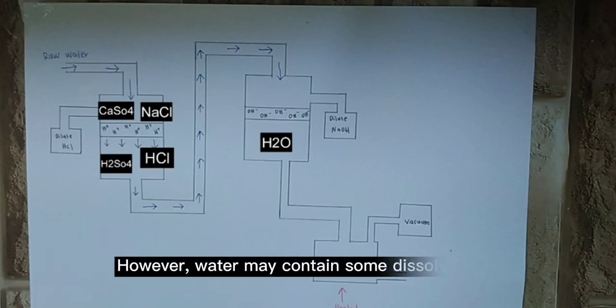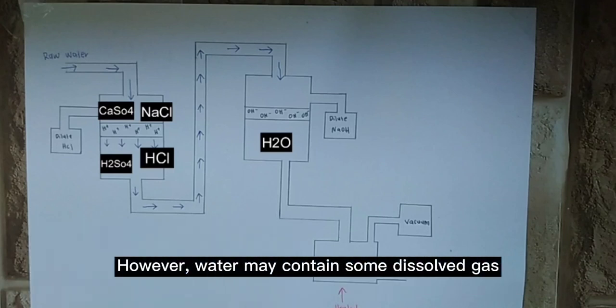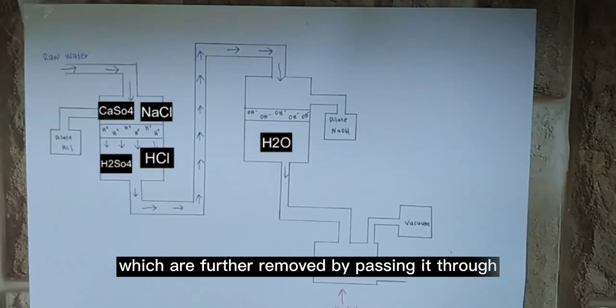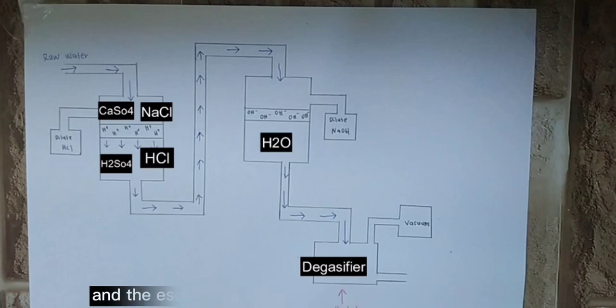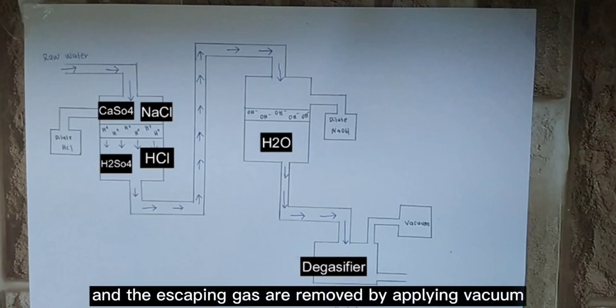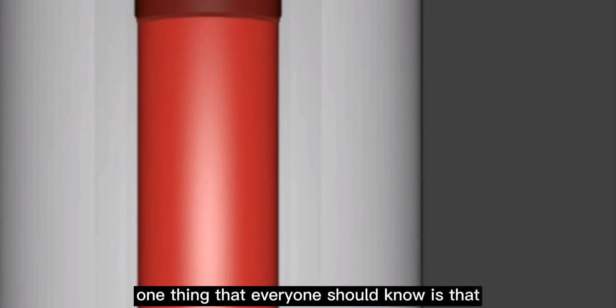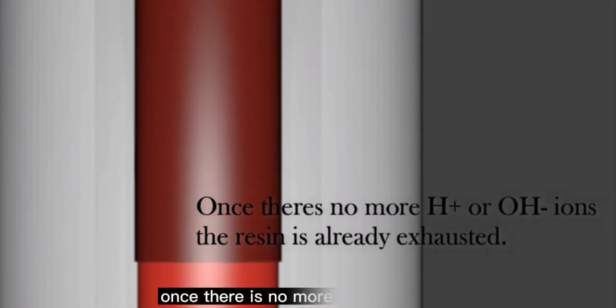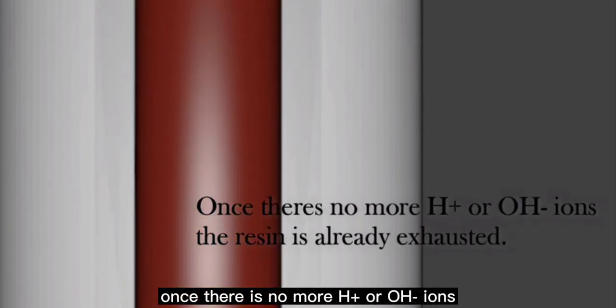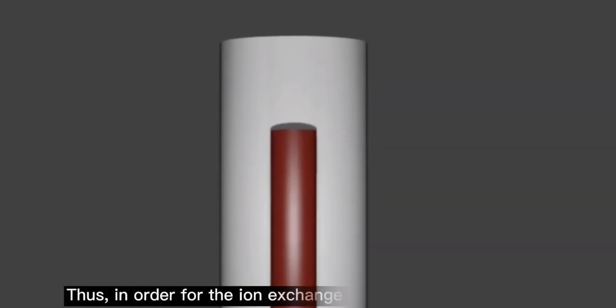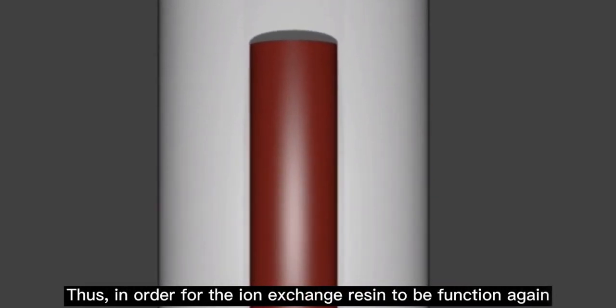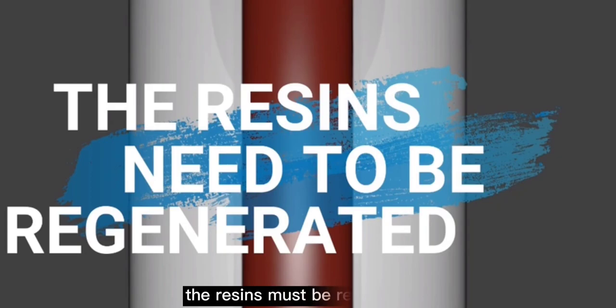However, water may contain some dissolved gases which are further removed by passing it through a degasifier where it is heated and the escaping gases are removed by applying vacuum. One thing everyone should know is that once there are no more H-plus or OH-minus ions, the ion exchange resin is already exhausted. Thus, in order for the ion exchange resins to function again, the resin must be regenerated.